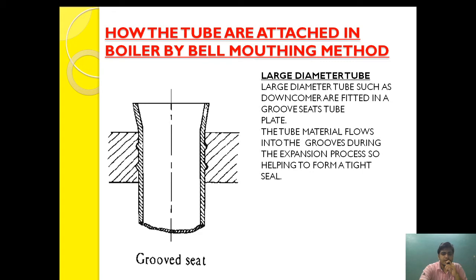For large diameter tubes, instead of only bell mouthing, a special groove seat structure is also provided. Large diameter tubes such as downcomers are fitted in a groove seat tube plate. The tube material flows into the groove during the expansion process, helping to form a tight seal and providing additional grip and support to prevent the tube from coming out.